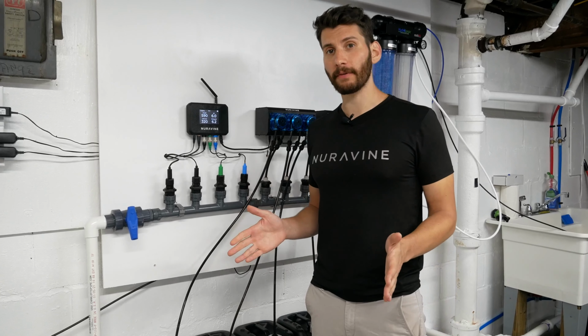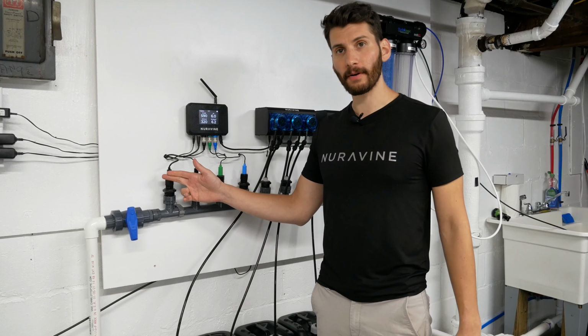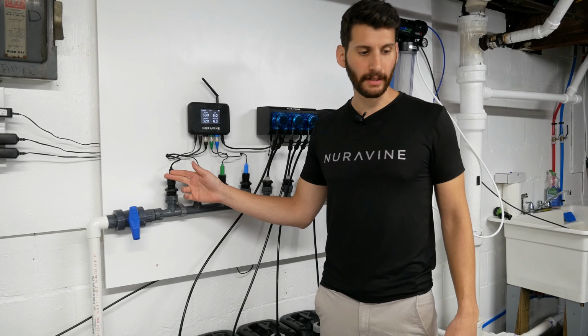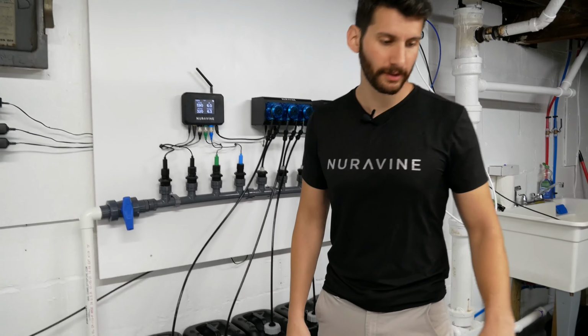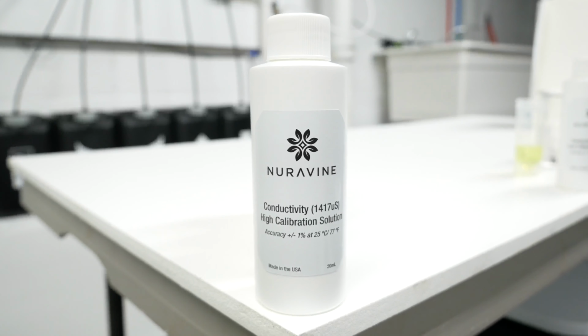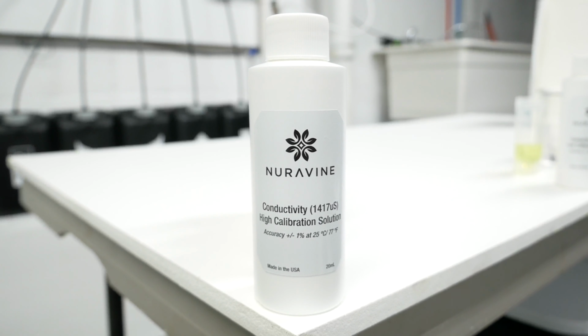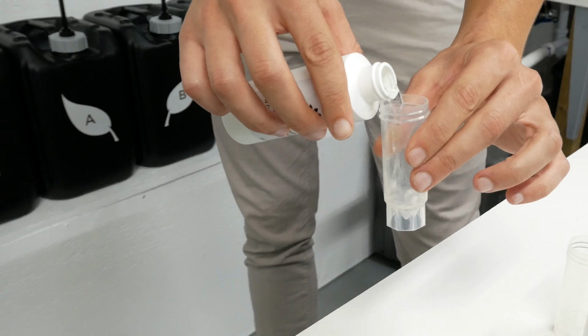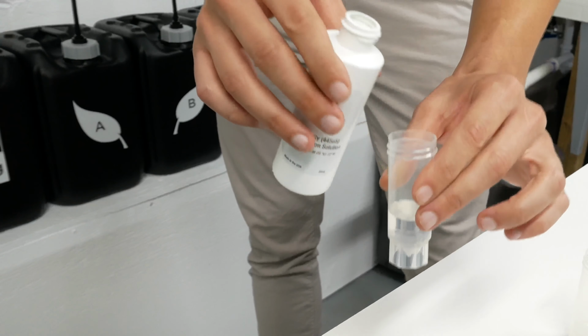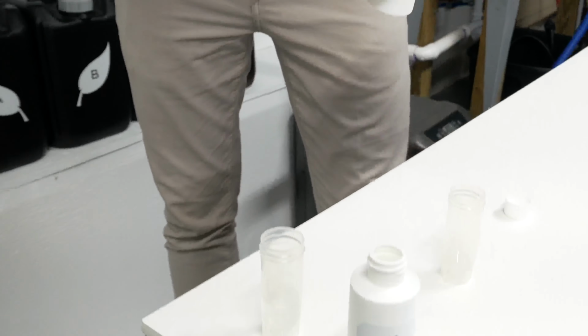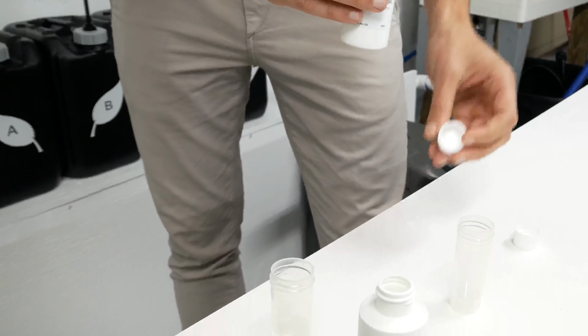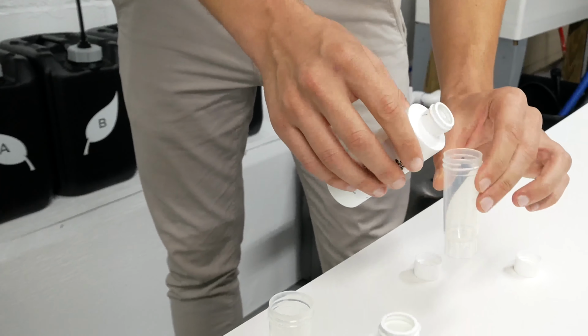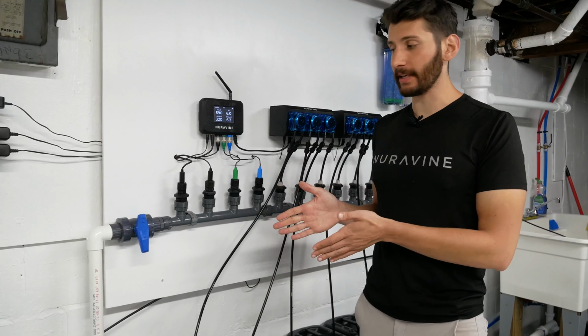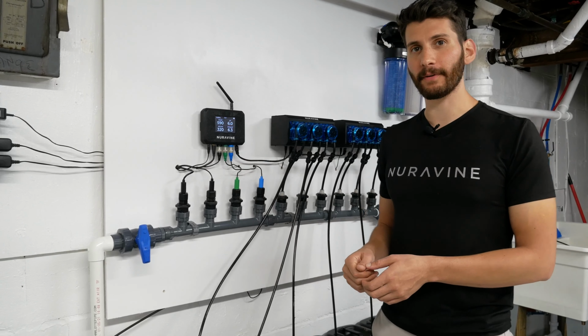So first off, we're going to be calibrating our EC probe. To do that, we're going to need our EC calibration solutions. We've got our low solution and our high solution. What I'm actually going to do is take these 2 solutions and pour them into these 2 cups right here. Now they're both clear, so make sure that you know which one's which, because if you don't, it's totally not going to work. So the next step is we're going to take the probe out of the manifold.